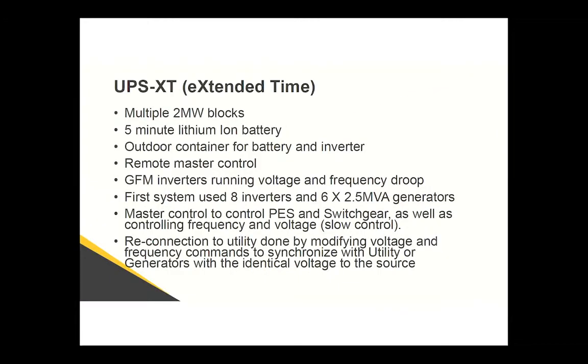So after doing that project, we started working on a new UPS system. We called it a UPS XT because we were extending the time from what we had gotten up to, which was a minute. And then we had time that was really set by batteries. We do most of that with a 5-minute battery, but we also had a half-hour battery at one of our early sites. So it's not limited by time any longer. We have multiple 2-megawatt blocks. We can containerize the 2-megawatt block with 5 minutes of battery in a 40-foot ISO container. And so I'll go outside with that.